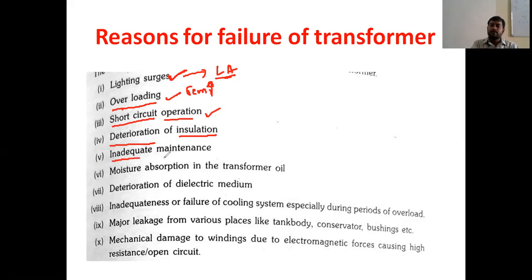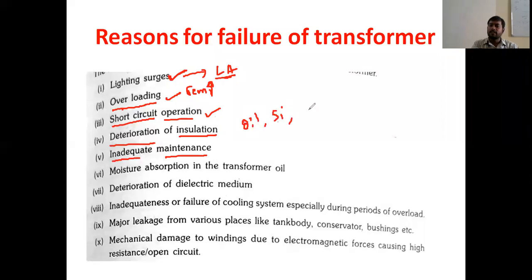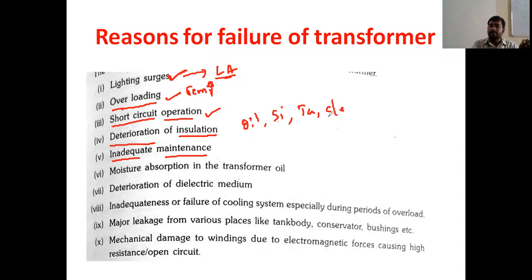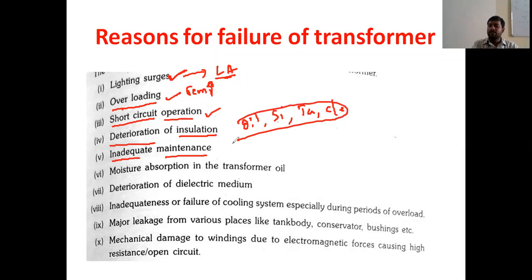Inadequate maintenance is another cause. Due to lack of proper maintenance — such as oil maintenance, silica gel maintenance, conservator tank maintenance, and cleaning — because of all these inadequate maintenance problems, the transformer will fail.